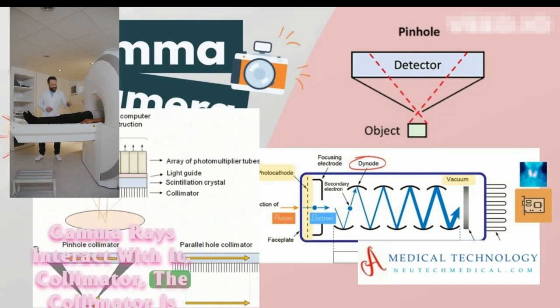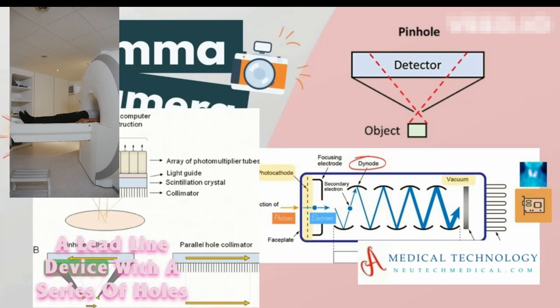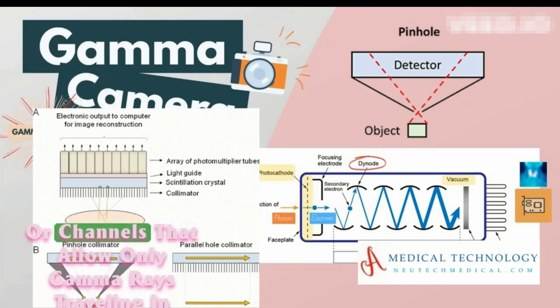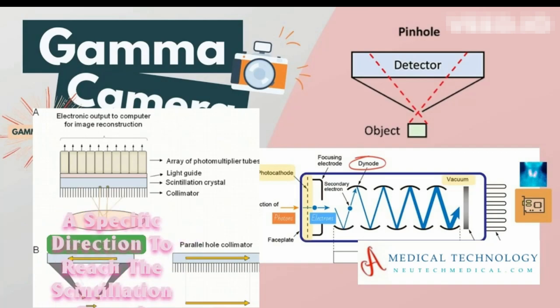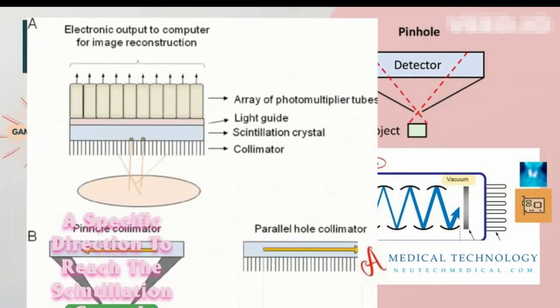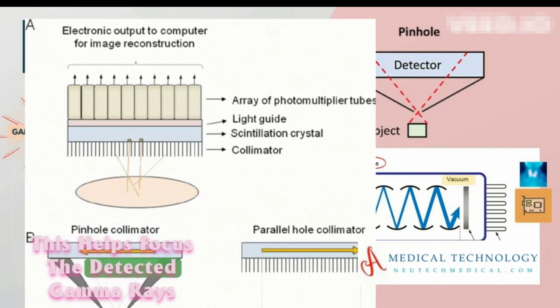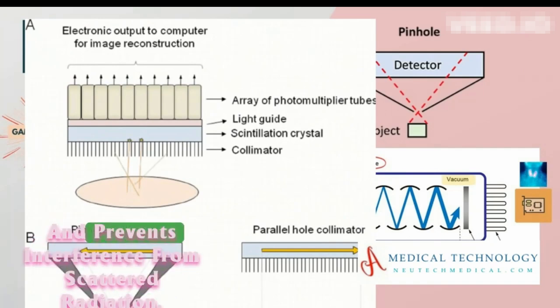Collimator: The collimator is a lead-lined device with a series of holes or channels that allow only gamma rays traveling in a specific direction to reach the scintillation crystal. This helps focus the detected gamma rays and prevents interference from scattered radiation.